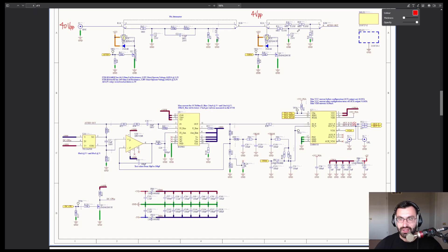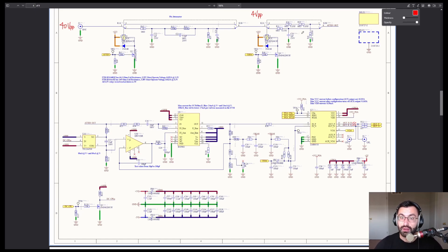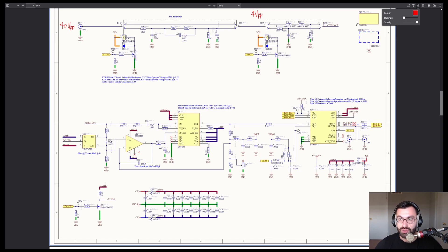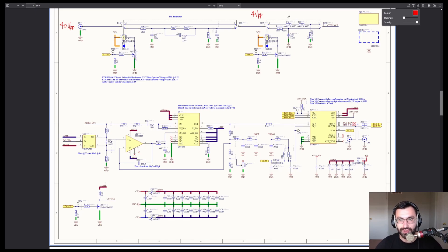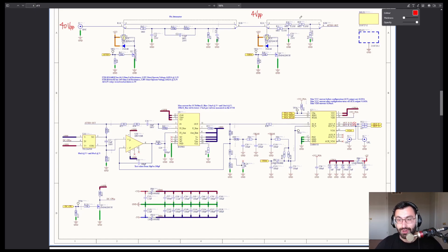That is an easier question to answer for the 50 ohm path, so let's start with that. In this path, you're not really limited by how much voltage is coming out of this attenuator. You're limited by the fact that you have essentially a 50 ohm resistor that you're putting a bunch of voltage through. So you're going to start burning a lot of power.